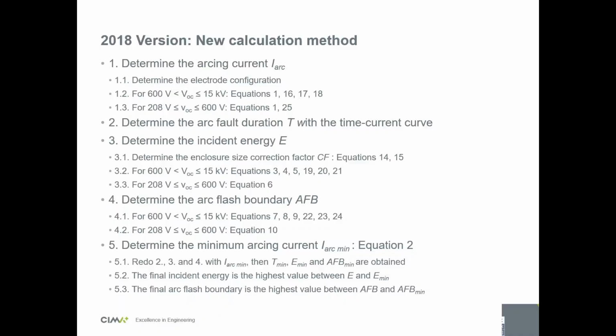And then you need to do a minimum arcing current. In the last standard, the minimum arcing current was always 85%, and it was only required under 1 kV. Now, in the new version, it's required for any voltage, and it's not 85% anymore. So it can vary depending on voltage. The IARC min can be, for example, 90% of the IARC. It can be 70% of the IARC. So it can vary with voltage now. So it's a bit more complex.